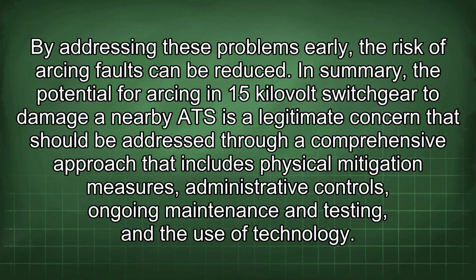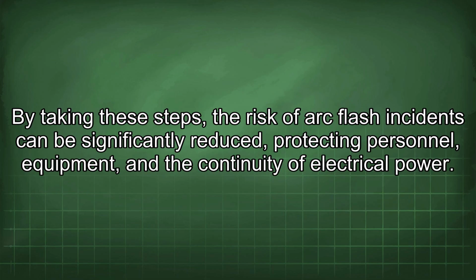In summary, the potential for arcing in 15 kilovolt switchgear to damage a nearby ATS is a legitimate concern that should be addressed through a comprehensive approach that includes physical mitigation measures, administrative controls, ongoing maintenance and testing, and the use of technology. By taking these steps, the risk of arc flash incidents can be significantly reduced, protecting personnel, equipment, and the continuity of electrical power.